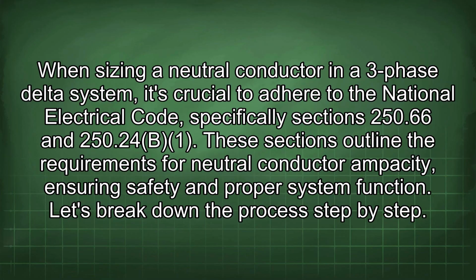When sizing a neutral conductor in a three-phase delta system, it's crucial to adhere to the National Electrical Code, specifically sections 250.66 and 250.24(B). These sections outline the requirements for neutral conductor ampacity, ensuring safety and proper system function. Let's break down the process step by step.